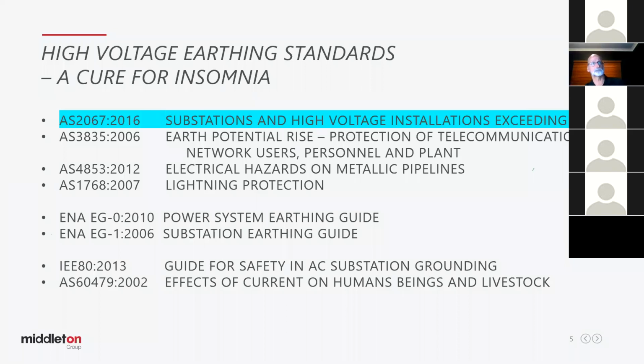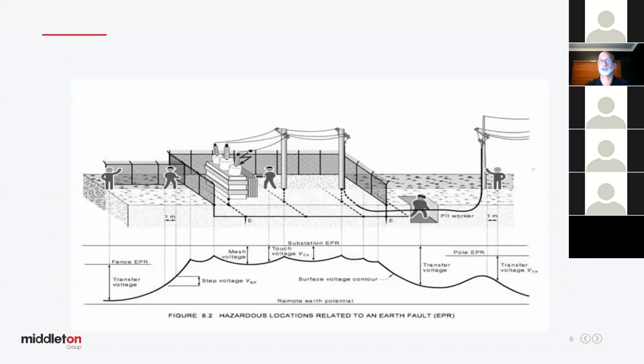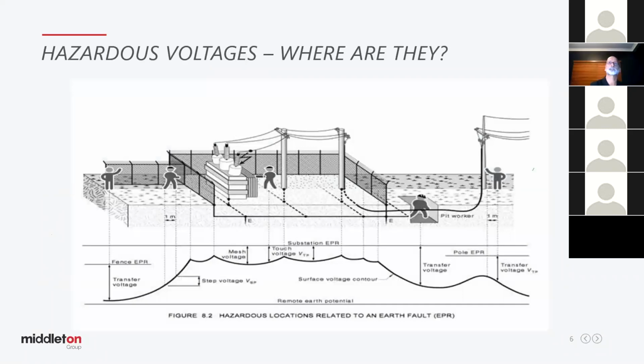Lightning is another study we do for earthing. Below that, you'll see a couple of earthing guidelines from ENA EG-0, EG-1, good reference documents, and a few international standards at the bottom there as well. There are seminal documents that, if you follow the history, feed into a lot of those standards above. So that's enough of standards. Let's leave them behind. So hazardous voltages, where are they?